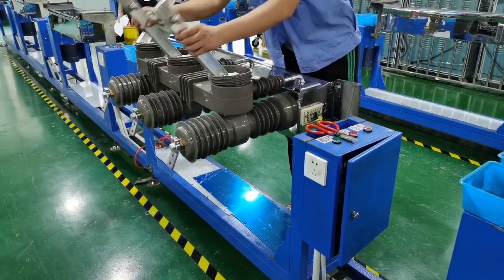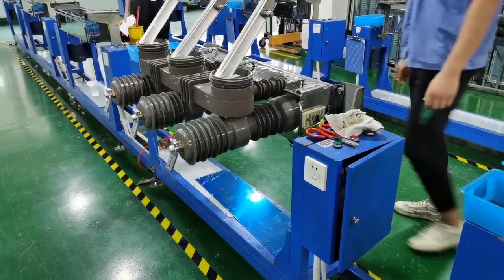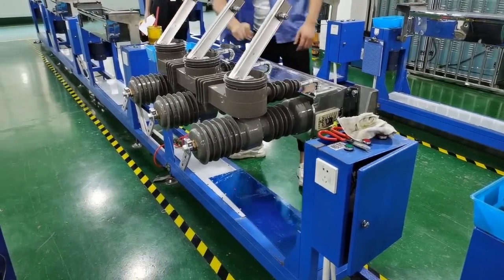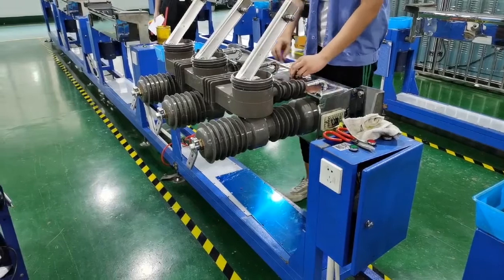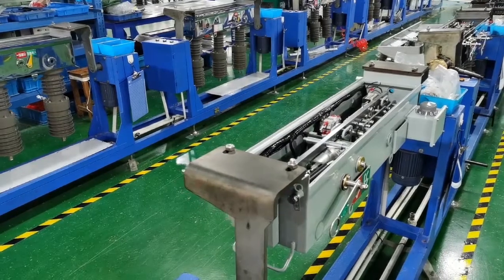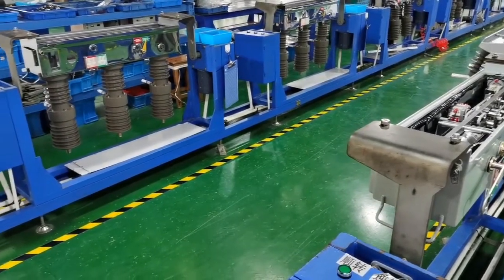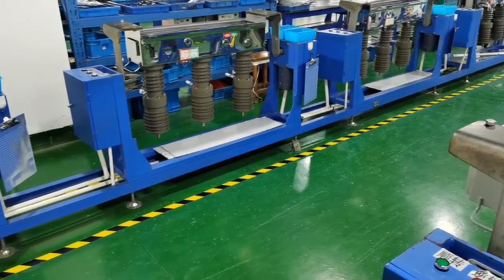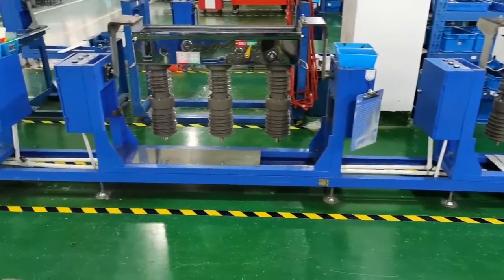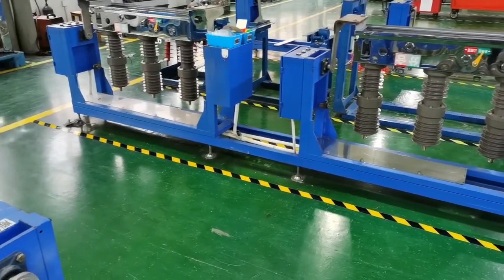The operating mechanism and vacuum interrupter are the two core component parts of the vacuum circuit breaker. Spring operation and permanent magnetic operation are both available. Mechanical life is 10,000 times per IEC standard. The dual operating mechanism combines spring type and permanent magnetic type; permanent magnetic operating mechanism life can reach 30,000 times. Spring type operating mechanism can always work regularly even when motor power is off.